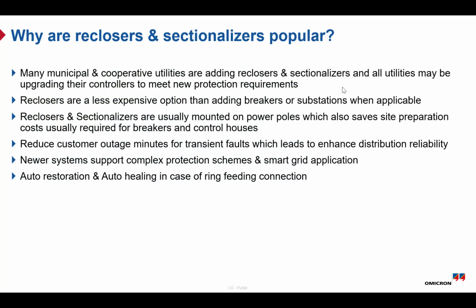So here, let us answer an important question. Why are reclosers and sectionalizers so popular? One of the main reasons is that they help to reduce customer outage time. Most faults in the distribution system are temporary or transient. So instead of sending a maintenance or operation team to manually restore the power, a recloser can clear the fault and restore service automatically within seconds.